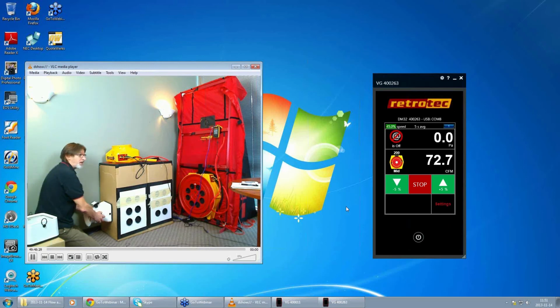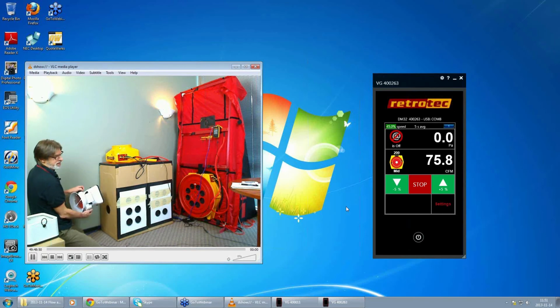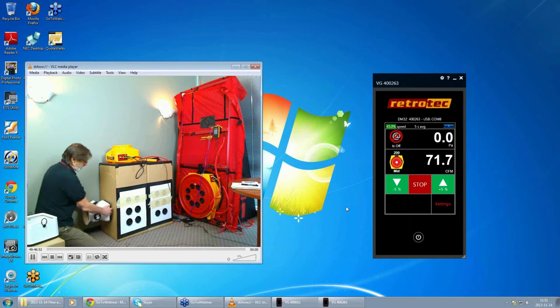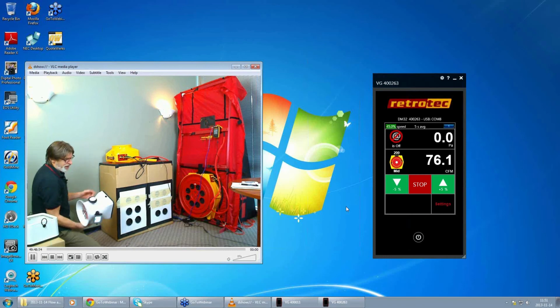80 CFM. Now I'm going to open it up. 86 CFM. So you can see the gap there. I got 80 CFM, 86 CFM, pretty close for the pretty huge gap that I had in there. So we're talking about a very sophisticated instrument. I think they've been developing this since 2008, so it's not something that they dreamed up yesterday.